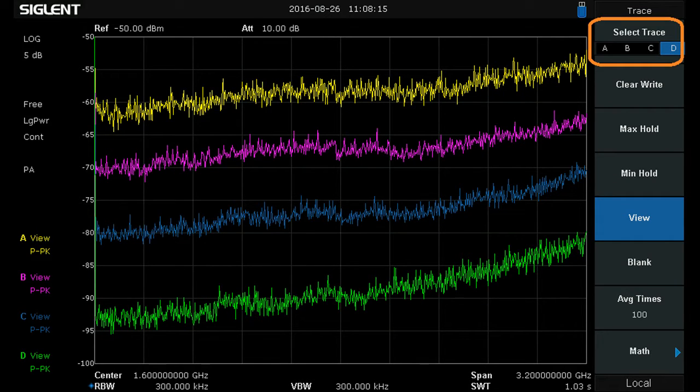This is four versus the three that is available in many other spectrum analyzers. Having the ability to view four traces simultaneously and being able to configure them each separately allows you to compare more of the traces that you've collected using different setups for the instrumentation or any particular parameters that you may have adjusted while performing data collection. It can be helpful when you're troubleshooting multiple scenarios or different measurement environments.